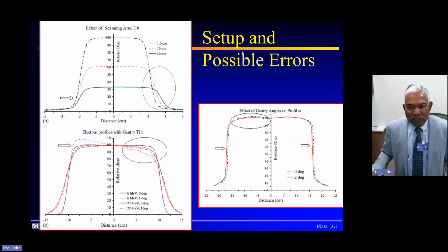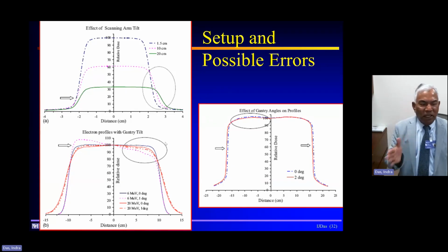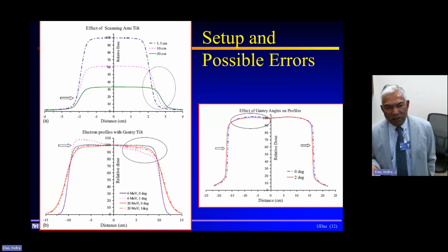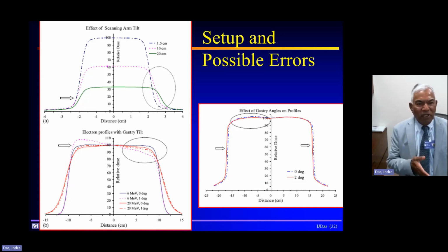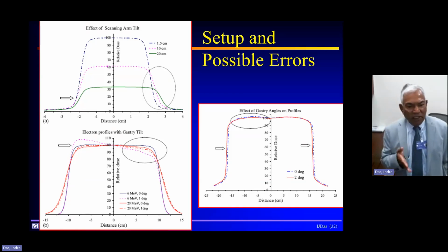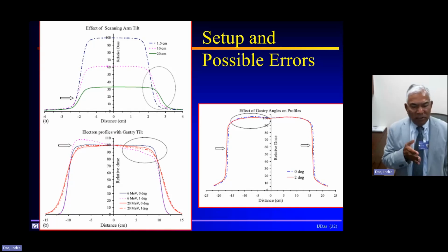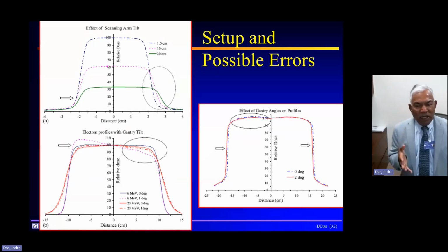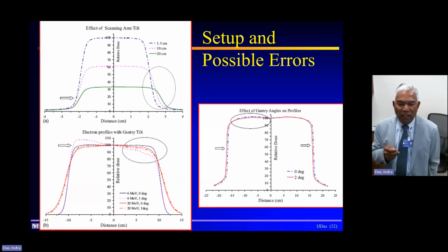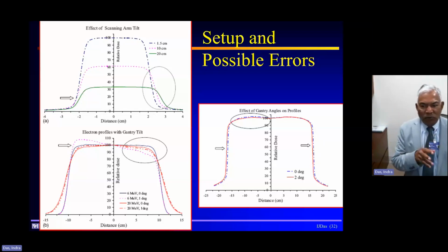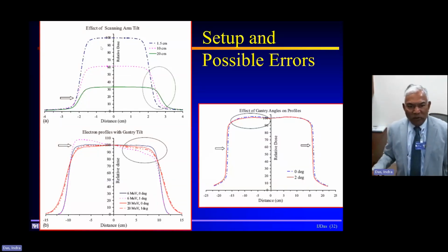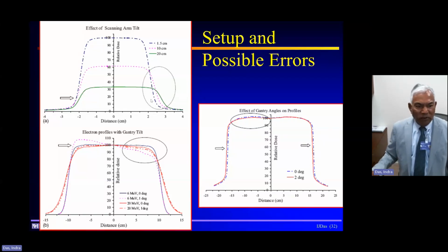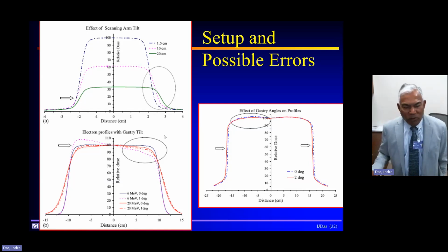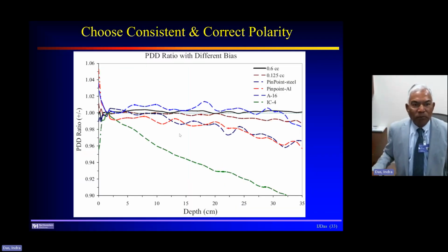The other thing is the setup of the water tank, when you are initially setting it up: the tilts, the angles, and all that. Now the modern scanners all have built-in tools. They can detect whether your tank is right, whether your gantry is correct. The gantry and tank have to be properly aligned, and you have to worry about those aspects. So just pay attention to whether there is a tilt on one side or the other. When you see abnormal situations, then just look at it.